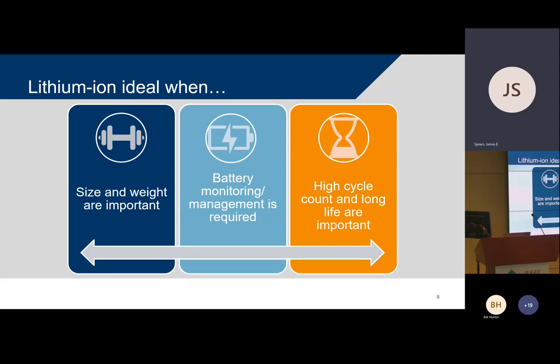Notice the term here is battery management, not just monitoring - this is required in all these lithium battery systems, both to manage the battery and to monitor it. It monitors voltages, currents, temperatures, and battery balance between cells in the string, but it's also required to manage: if there's a thermal condition getting too hot, or voltage becoming unbalanced, or float current too high - anything potentially dangerous - it will throw an alarm either through the UPS or directly.